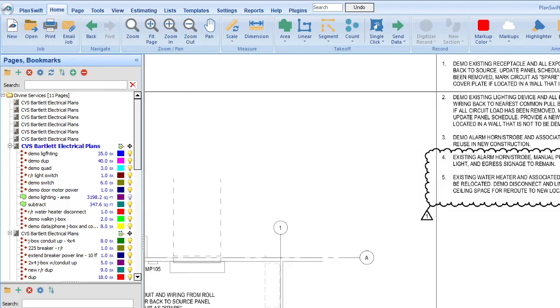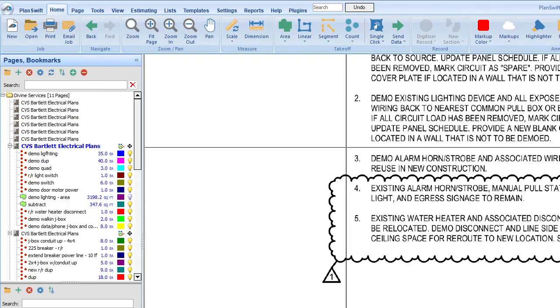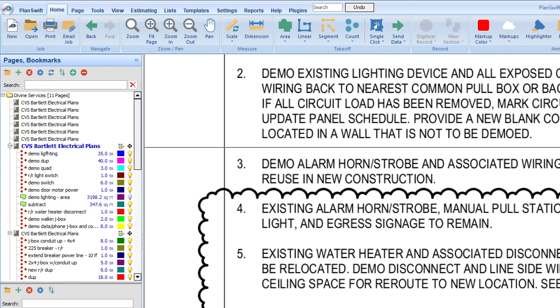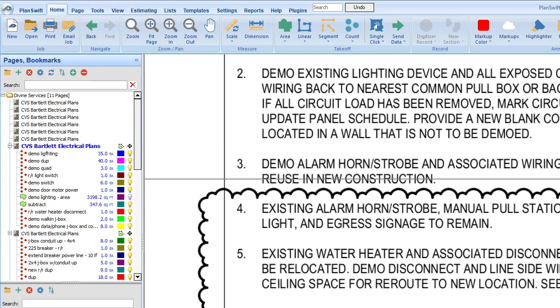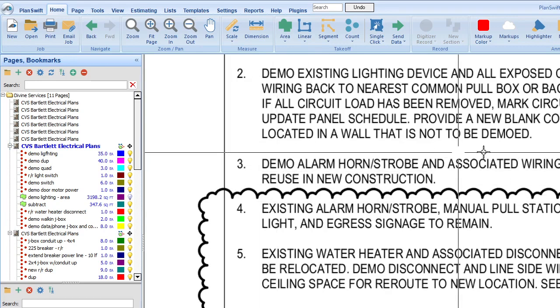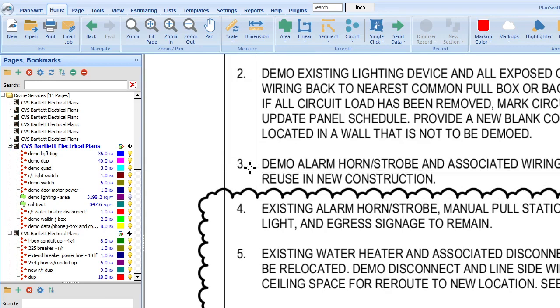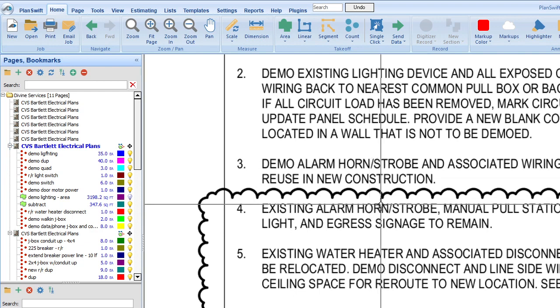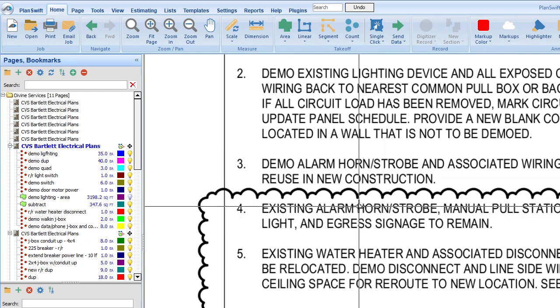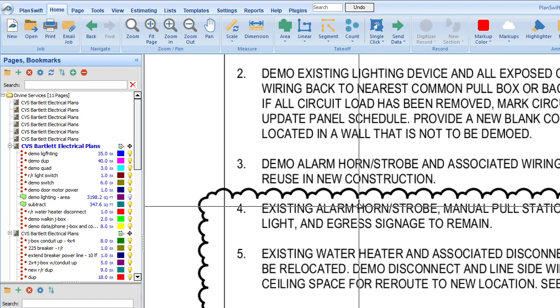So let's finish reading the notes. Number three, demo alarm horn, strobe, and associated wiring. Save for reuse. Okay, so when you are demoing for reuse, you're a little more careful with the demo, and so you're going to give it a little more time than you would for regular demo. So regular demo, you can rip it out, damage it in some way, and it's really not important because you're not reinstalling it. You can just cut it, cut the wires, whatever. But when you're going to reuse it, you're going to give yourself maybe double the time that you would.